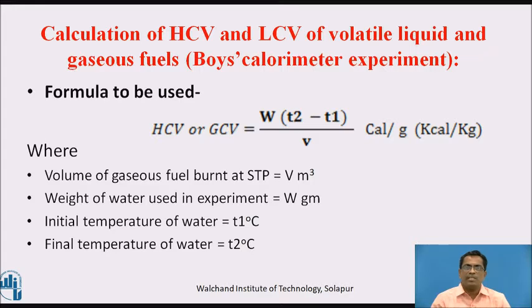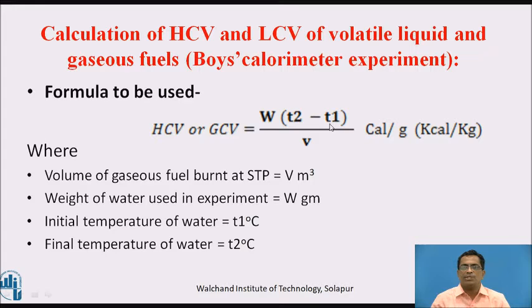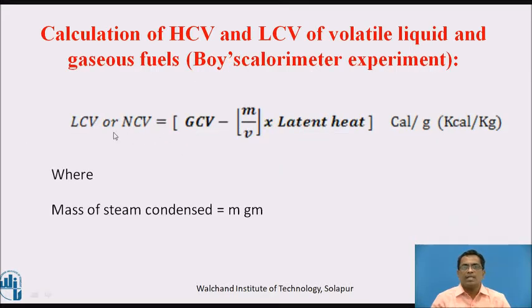Calculation of HCV and LCV by Boy's calorimeter experiment. The formula to be used is: HCV or GCV = W × (T2 − T1) / V, where W is the weight of water used in the experiment, T2 is the final temperature, T1 is the initial temperature of water, and V is the volume of gas used for the operation. LCV or NCV = GCV − (M / V) × latent heat, where M is the mass of steam condensed.